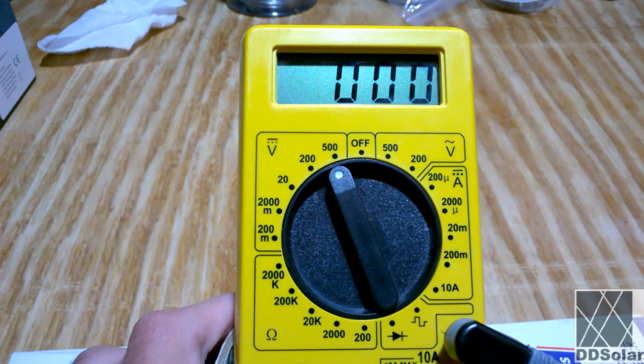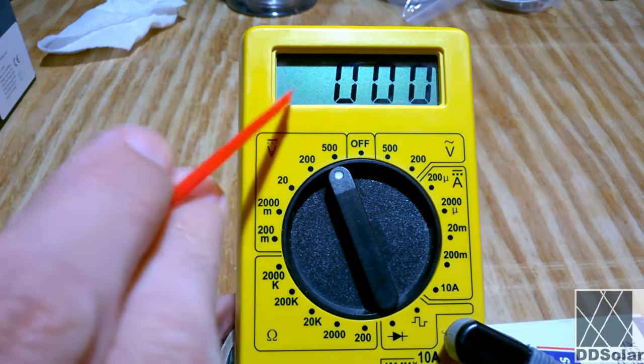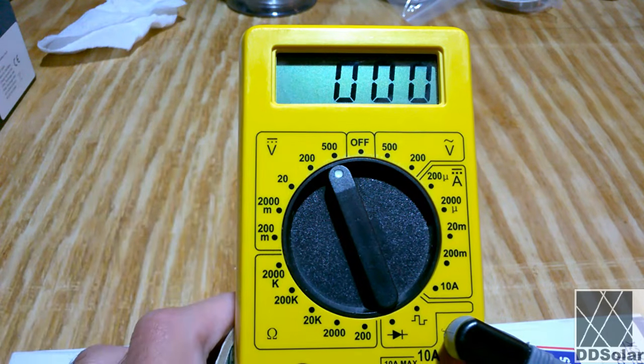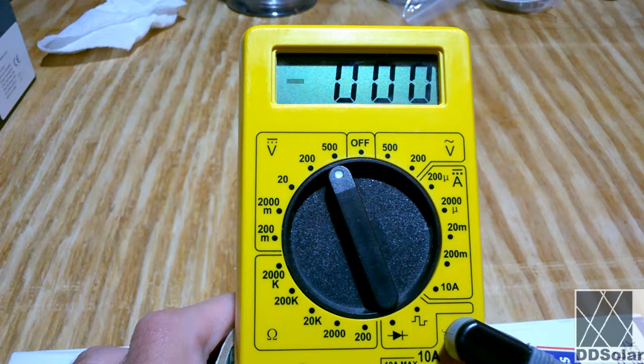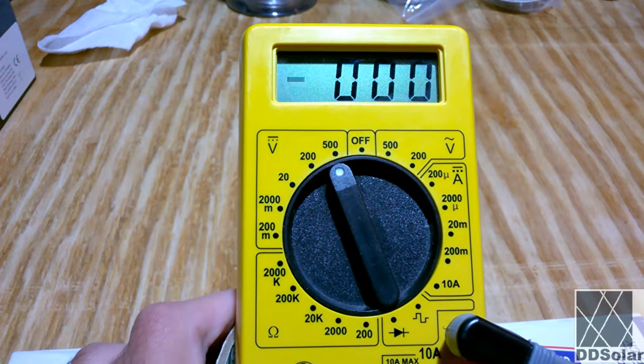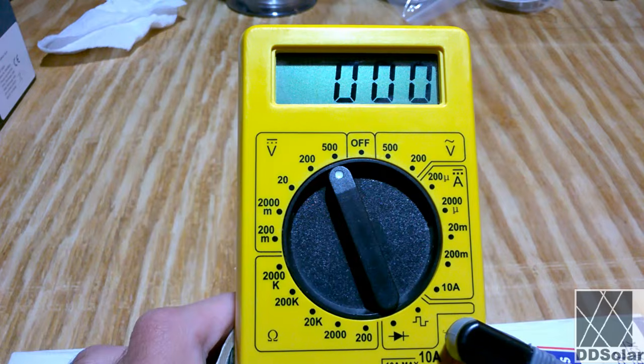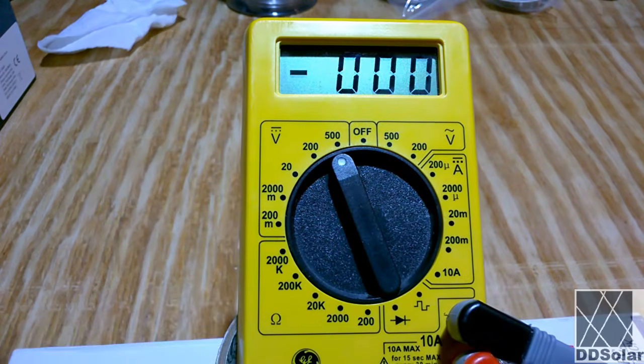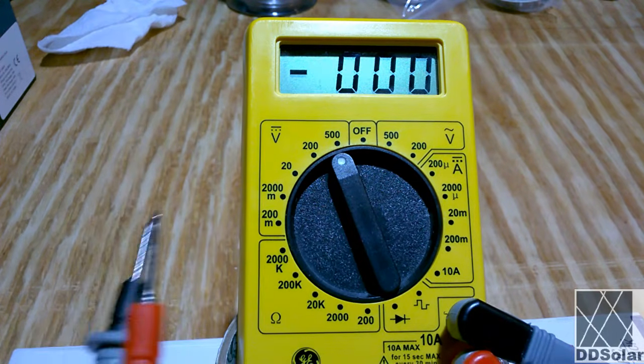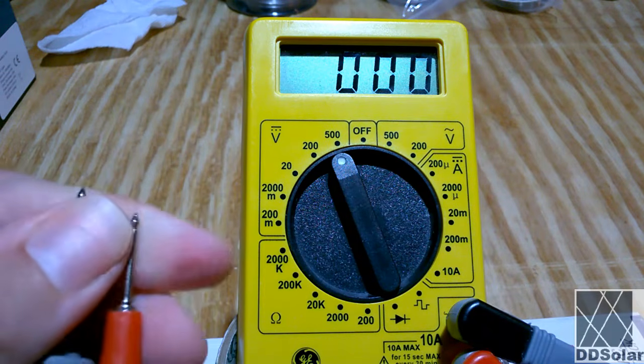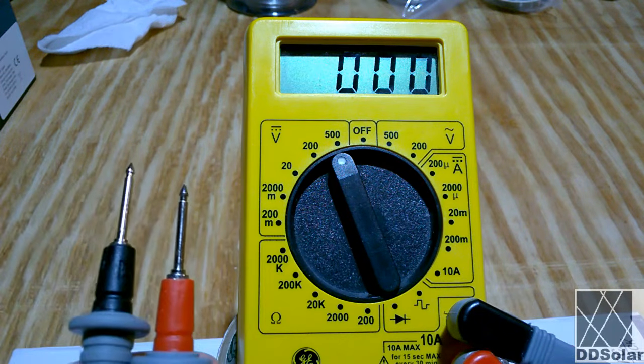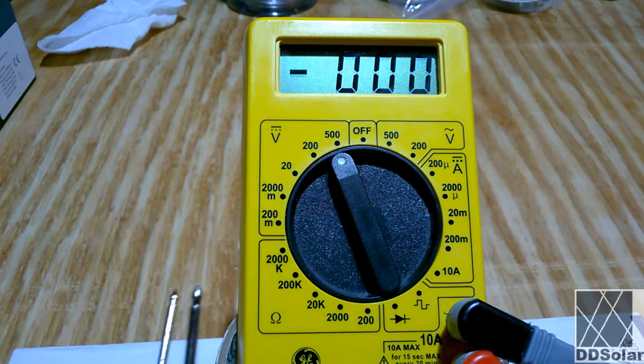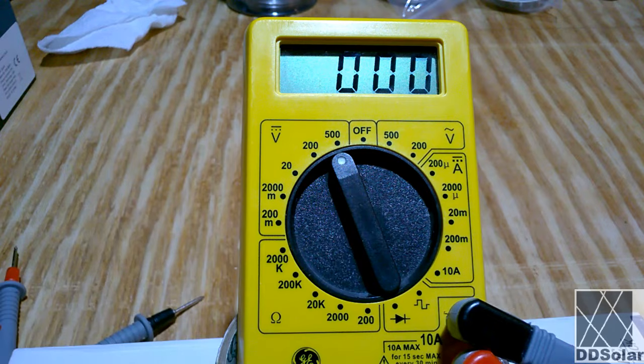And the reason you're seeing the polarity sign flash regularly, that's right here, this indicates positive or negative, is because the meter is quite sensitive and it's trying to constantly measure the voltage. And believe it or not, even when the probes are not connected to anything and are just laying on the ground, here's the probes right here, they actually can generate a voltage. And if you put the meter on a more sensitive scale, it's possible to even get that number to change. So you'd be putting a tiny bit of voltage into these probes from just your fingers or whatever stray voltage you're picking up. Now that we're on 500 volts DC, let's measure a voltage source.